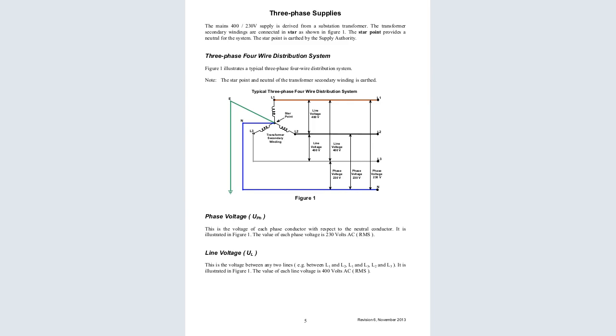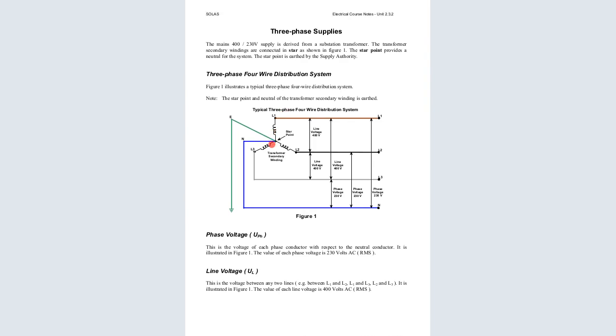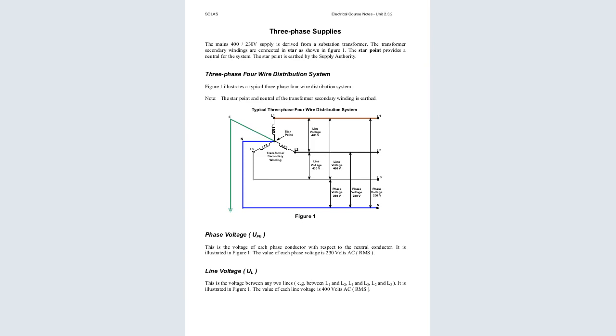For this, is it a star or a delta? This is a star. You can see it is like a star. This is the winding. This is for the one phase. This is for another phase. This is for another phase. So it is star. So you can see the neutral, the way the neutral is tapped. The neutral is in color blue. You can see the neutral is tapped, and the earthing is in color green. But the phases are here. Phase 1, that is line 1. Phase 2, that is line 2, and phase 3, that is line 3. So you can see them.